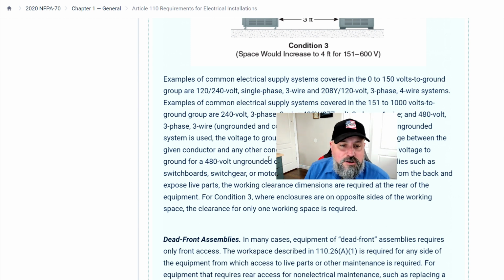Where an ungrounded system is used, the voltage to ground by definition is the greatest voltage between the given conductor and any other conductor of the circuit. For example, the voltage to ground for a 480 volt ungrounded delta system is 480 volts. For assemblies such as switchboards, switchgears, or motor control centers that are accessible from the back and exposed live parts, the working clearance dimensions are required at the rear of the equipment.